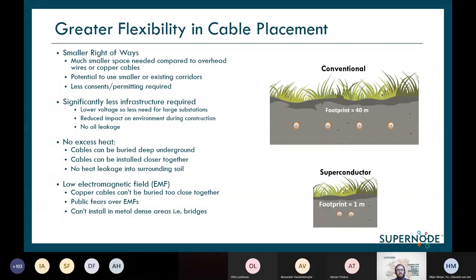Electrical resistance is related to heat dissipation from conventional cables, so spacing is required to allow this heat to dissipate and let the cable continue operating as expected. The other factor is the electromagnetic fields generated by conventional copper cables. This is not an issue with superconducting cables, so they can be spaced closer together, and public perception concerns around EMFs also don't apply to superconductors.